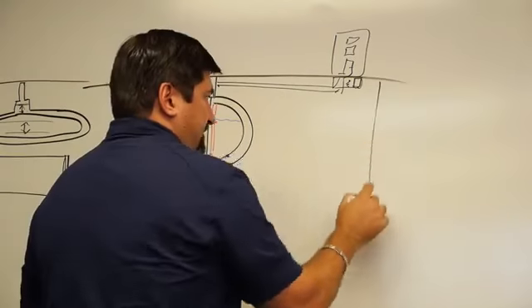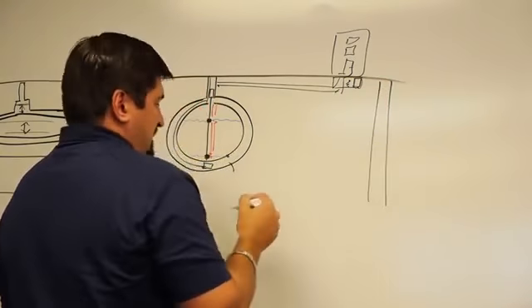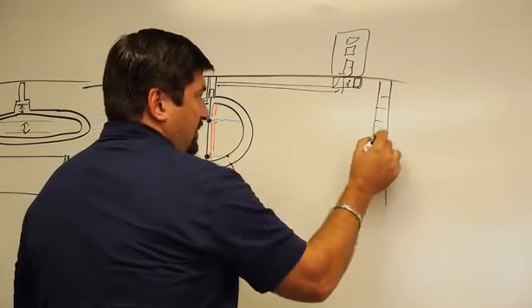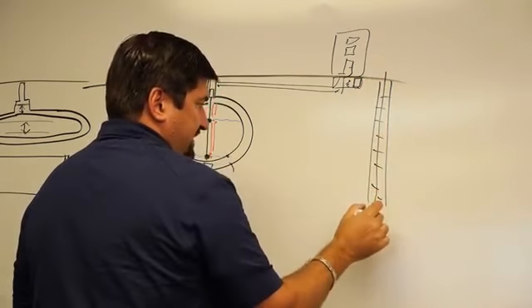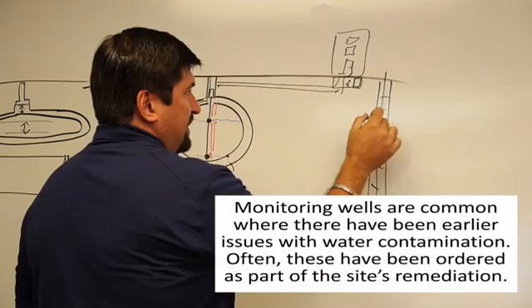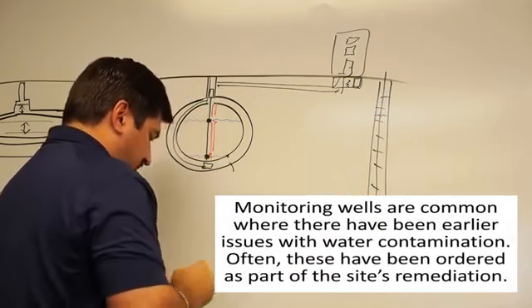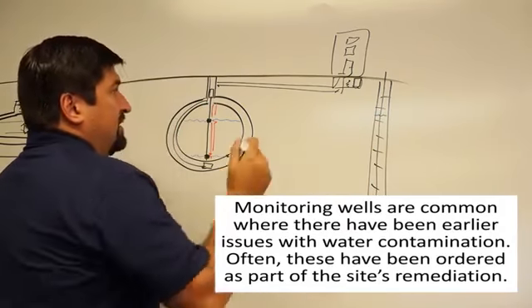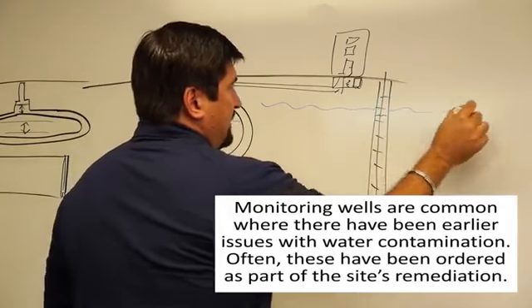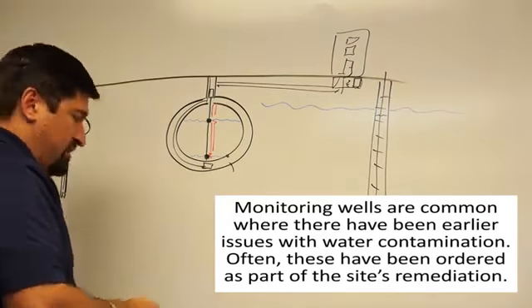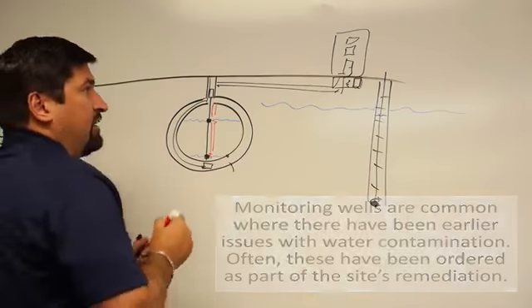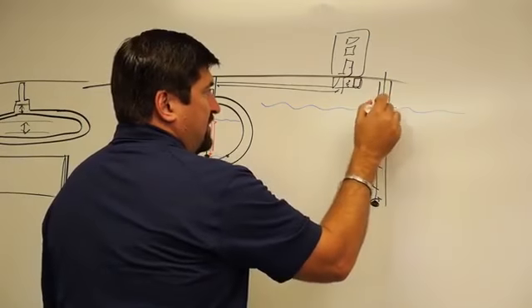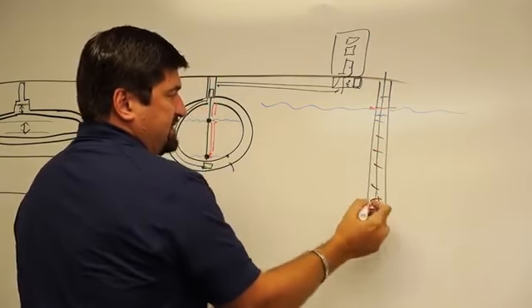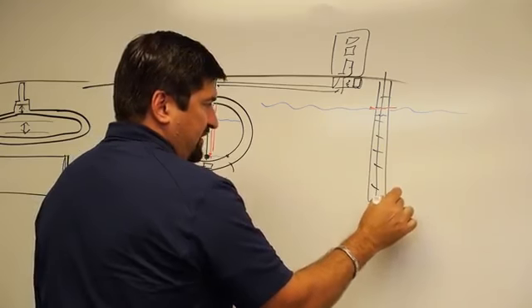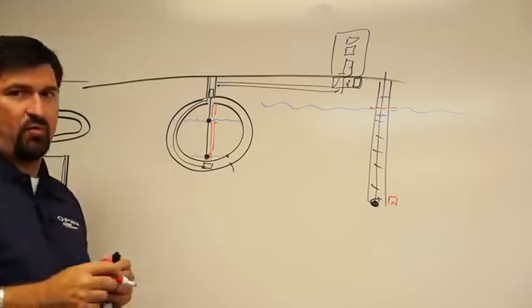You can have monitoring wells. So if I have a monitoring well at a site, I do the same thing. I'm going to put a sensor down here with a float, and I'm monitoring the water level at the facility. So basically what I'm doing is monitoring the groundwater to make sure that there's no hydrocarbon floating on the surface that comes in contact with this sensor, but you're also making sure that this float is always submerged in water.